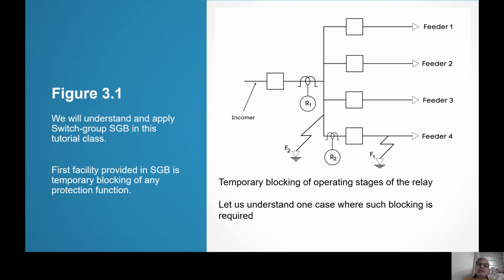And while giving backup, we have no other go, but we have to go for time delay. And we were using time discrimination margin of 0.25 second, that is 250 millisecond. Nowadays, you see, we are talking about national grid. The whole of India is connected with grid. So if there is a fault in Ahmedabad, Assam is also feeding fault. Kanyakumari is also feeding fault. And Kashmir is also feeding fault. So in that era, 250 millisecond is a big time. It cannot be allowed. Right?